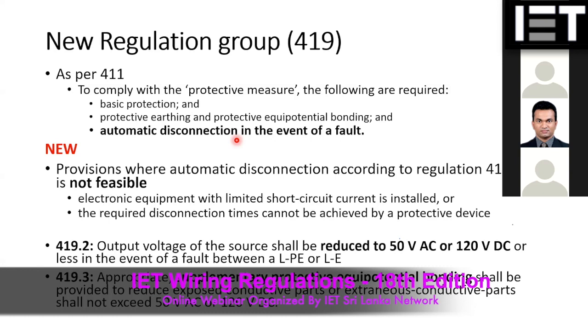Normally you have to have the PE conductor for all the equipment. It's a mandatory requirement. But if you cannot satisfy the automatic disconnection requirement mentioned in regulation 411, then you have to have supplementary bonding, so that you confirm there will be equipotential everywhere. So not only the PE conductor, but also supplementary bonding, so that you are confirming the entire installation is with equipotential bonding. So that is a new addition to the standard.